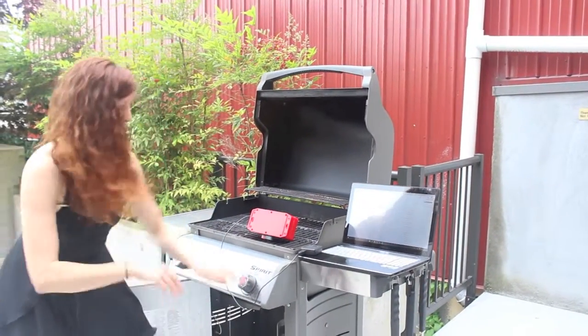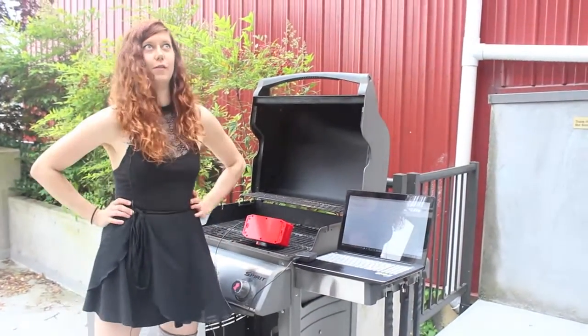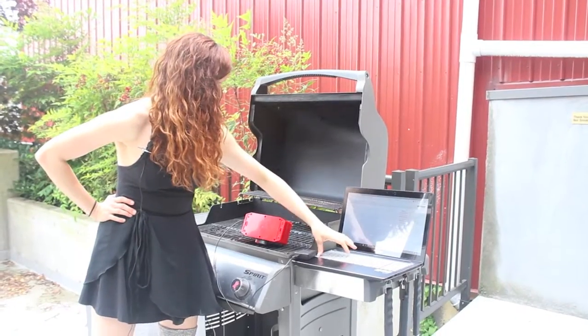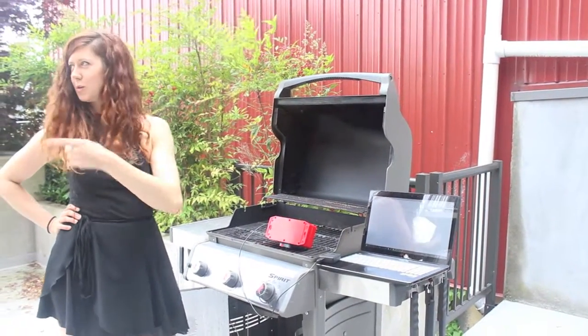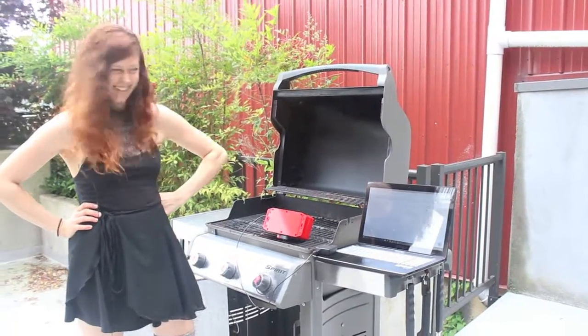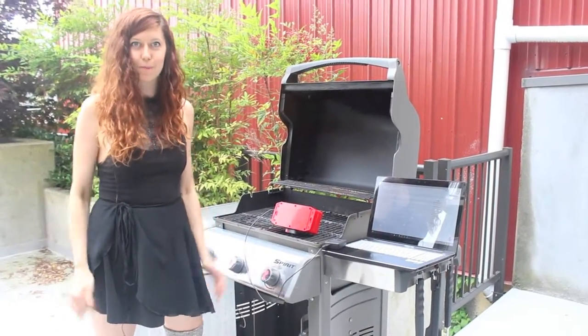I'm going to go ahead and turn the tank off, and hopefully that'll turn off eventually. That smells bad. Look at that — so the natural gas reading hit almost 2000, which is really, really high. The liquid propane went up to about 630, and CO changed very, very little. So that's what we would expect. Super cool!